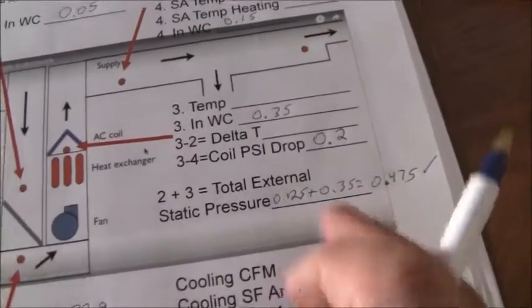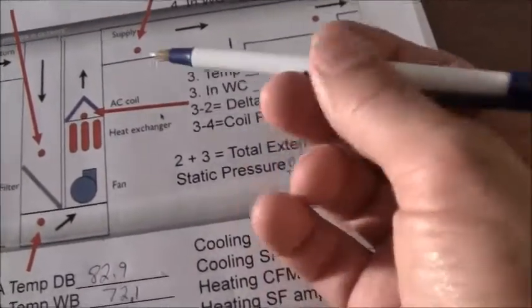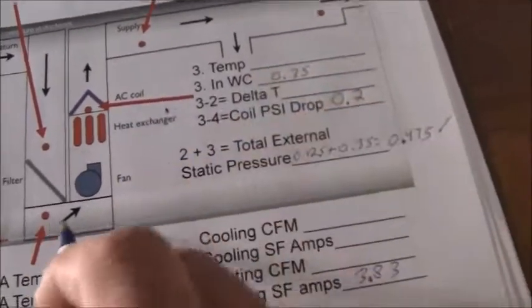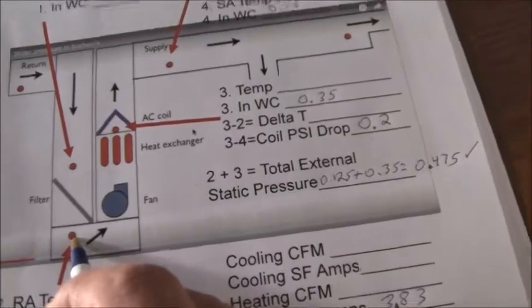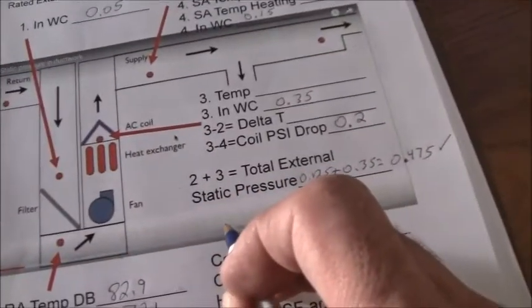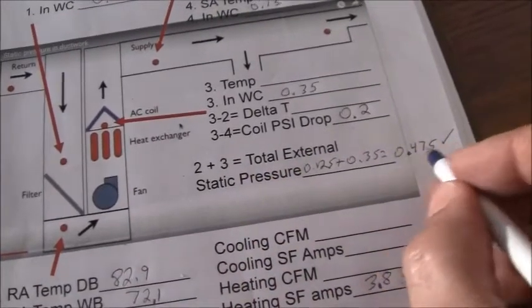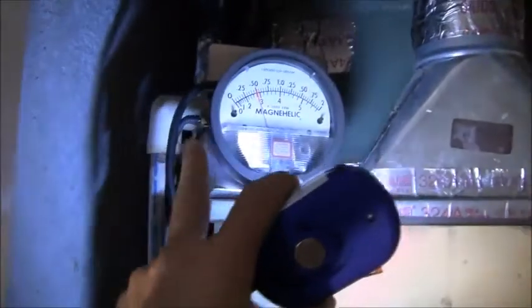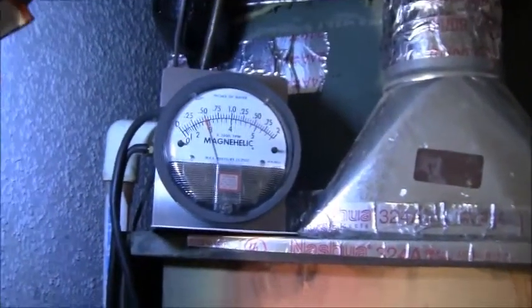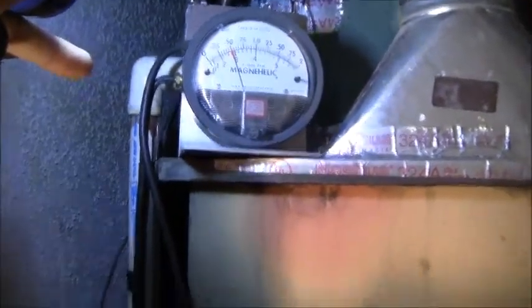Now, I want to do another check. I want to check external to the heat exchanger. So I want to put in a sample point low here and high here, and see if it equals 0.475. So that's what I'm going to do right now. I got the low port, the one on the bottom, coming down, and I plug that into the side of the unit, which is after the filter. Then the high side of the magnehelic gauge, which is the top line, is plugged in right there, on the upstream side of the AC coil.